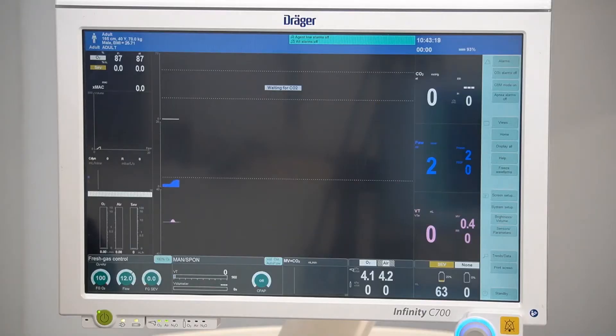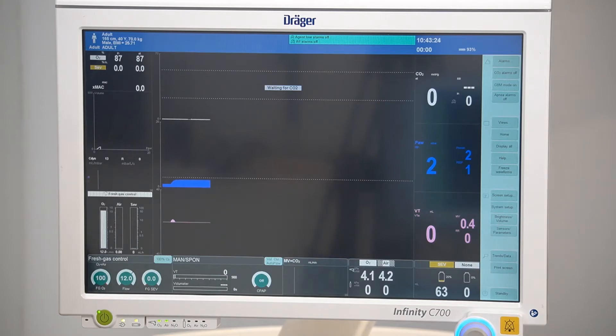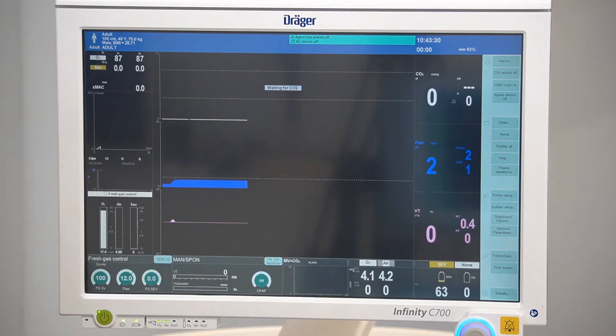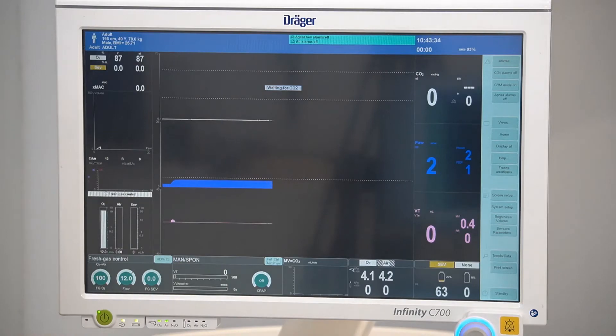After switching from system standby to operation, all non-technical alarms are deactivated for one minute to allow sufficient time to select a suitable setting. This is confirmed by the message 'all alarms off' in the header bar.